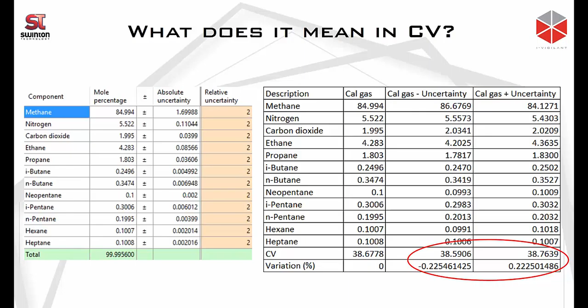Now, a lot of pipelines say that the maximum CV uncertainty that's allowed for a GC to measure is plus minus 0.2%. But regardless of this requirement, many operators still order calibration gas that has a relative uncertainty of 2%, and they get away with it. The reason they get away with it is because this kind of calculation isn't done. If this kind of calculation were done, that calibration gas should never have been installed in any installation. So at least what we recommend is a calibration gas with less than 1% uncertainty on each individual component, so that you have a reasonably low uncertainty when we start measuring the actual process gas.